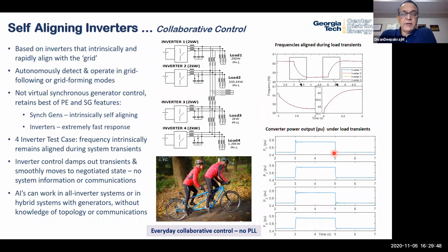We've been working on principles we call collaborative control and the concept of self-aligning inverters, where the inverters can autonomously detect and operate in either grid-following or grid-forming modes. You can actually have almost variable, adaptive inertia, which allows you to track big changes but still stiffen the system. So it's a very highly nonlinear control. What we find is that it really tends to stabilize the system.